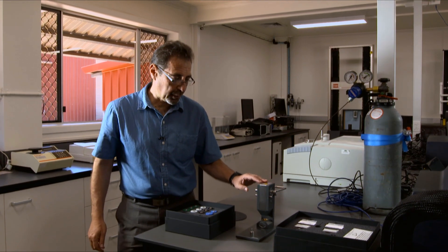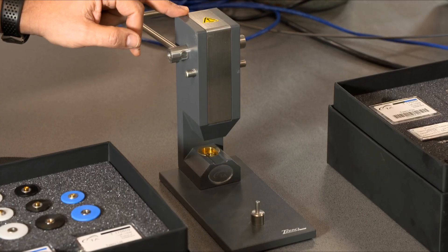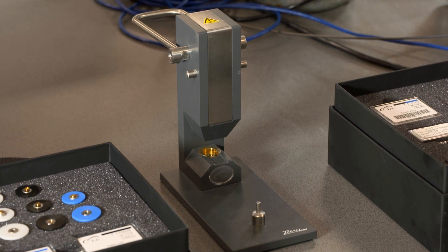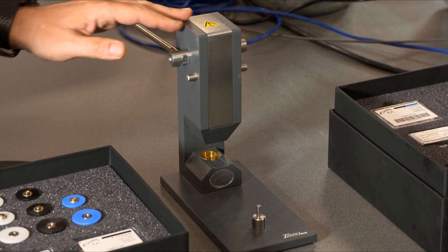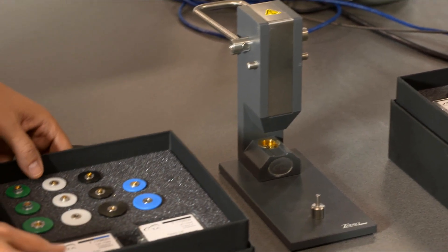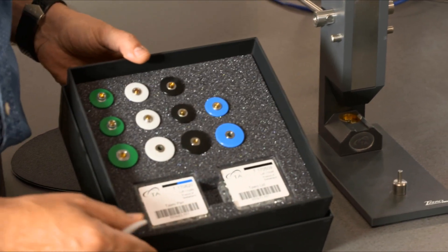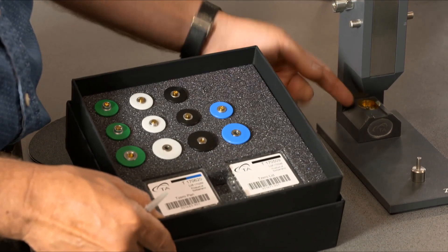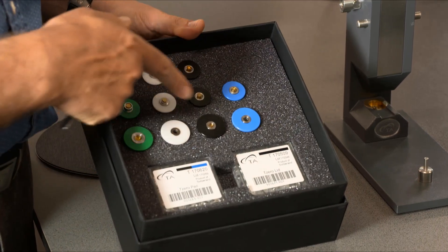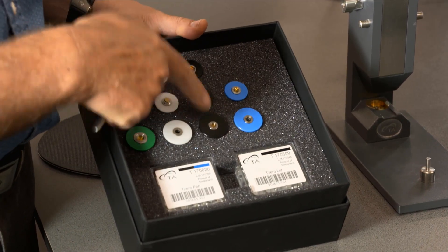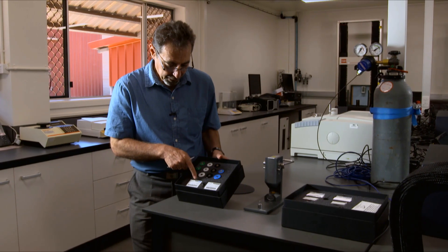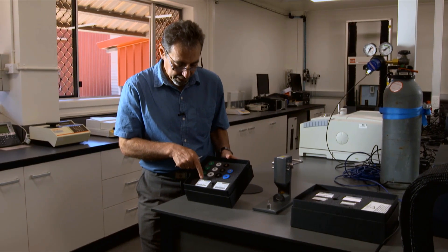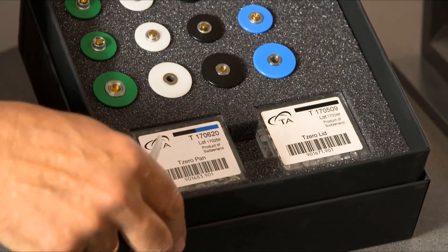Tzero Press is used to crimp the samples for a DSC instrument. It comes with a set of dies for the lower part and for the top part. As you can see, dies are color-coded and your boxes with pans and lids will be color-coded too.